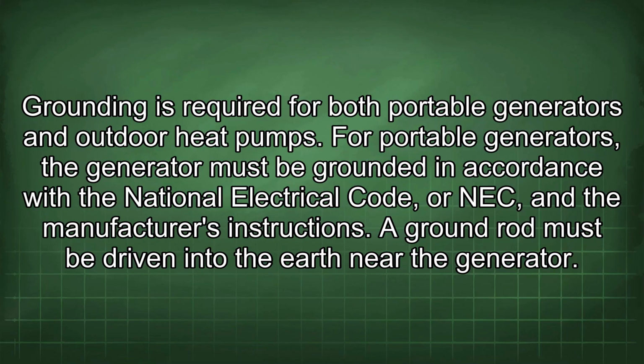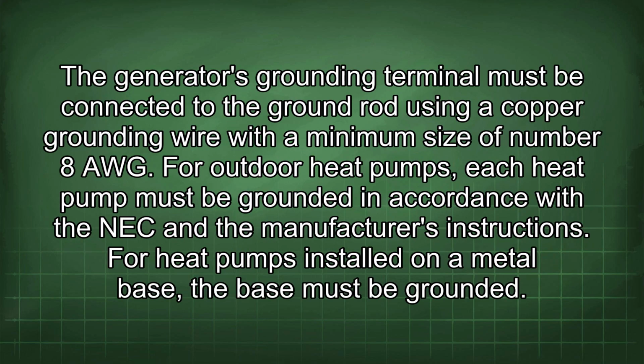Grounding is required for both portable generators and outdoor heat pumps. For portable generators, the generator must be grounded in accordance with the National Electrical Code, or NEC, and the manufacturer's instructions. A ground rod must be driven into the earth near the generator.